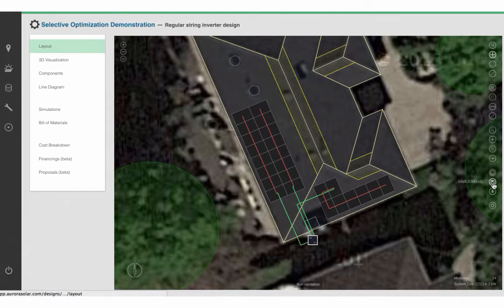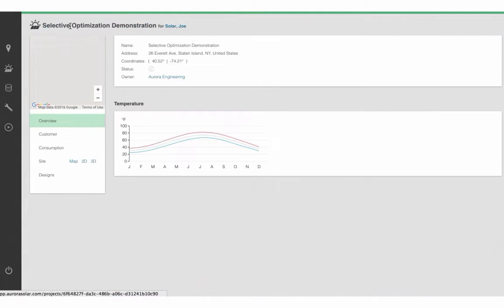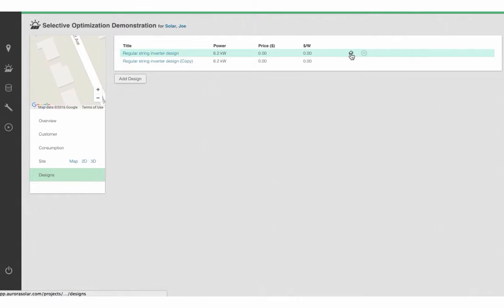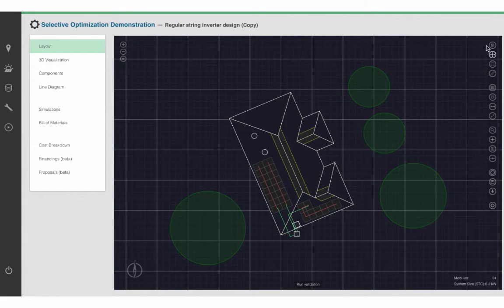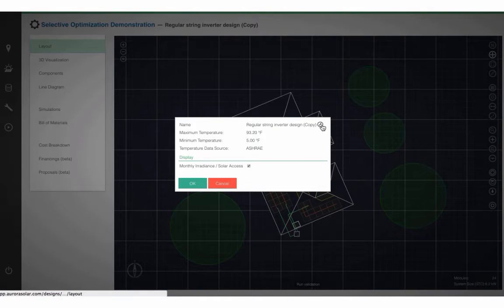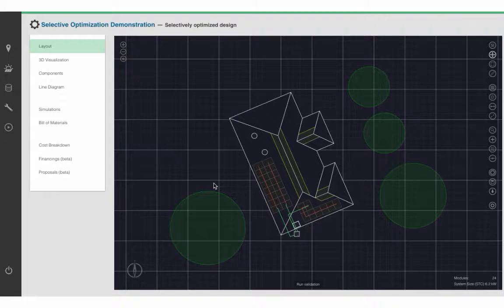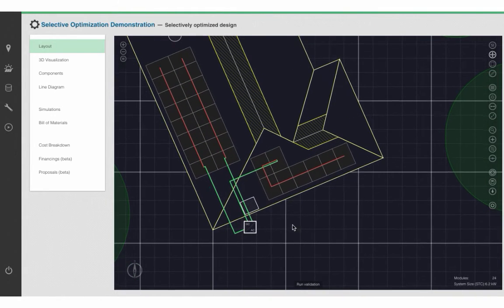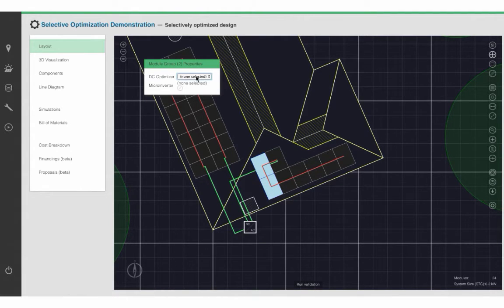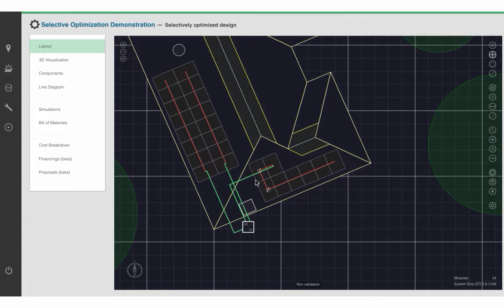I will go ahead and save this design, and now I am going to clone it and change the name of this new design to 'Selectively Optimized.' What I'm going to do is select these two modules over here, right-click on them, and select a DC Optimizer — in this case the Tigo TS4. The idea being that this is an area that experiences some pretty severe shading, and by selectively optimizing those modules, we can avoid them taking down this entire string.